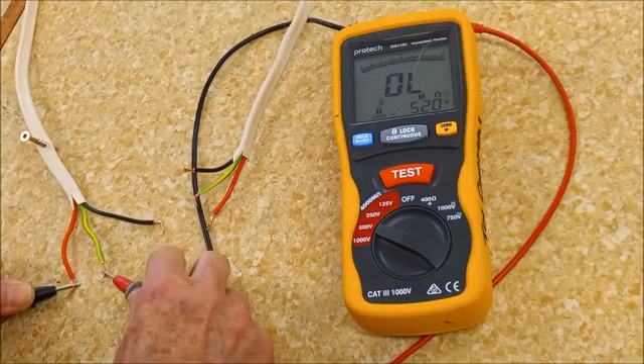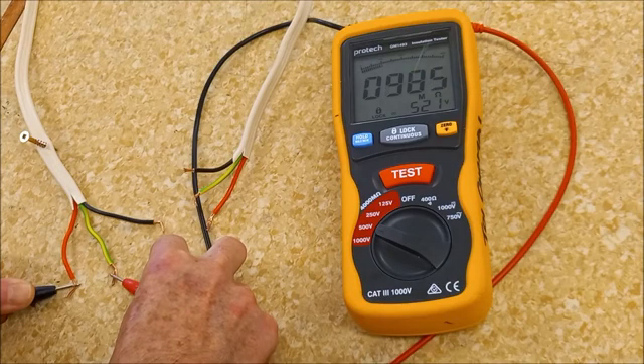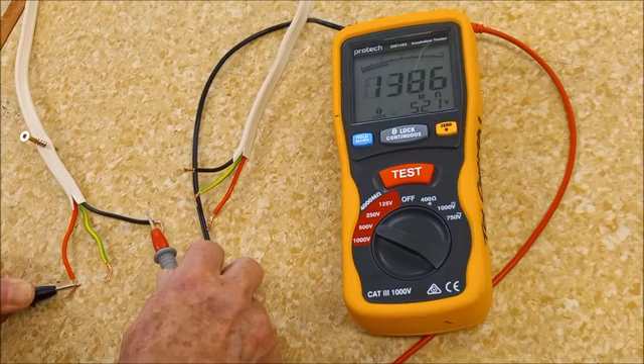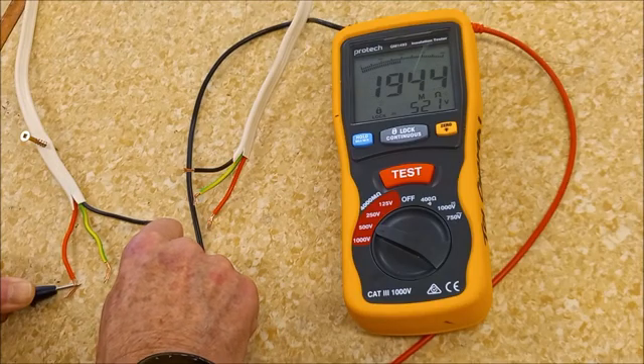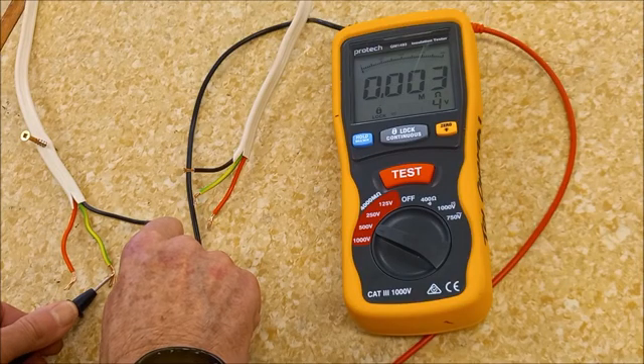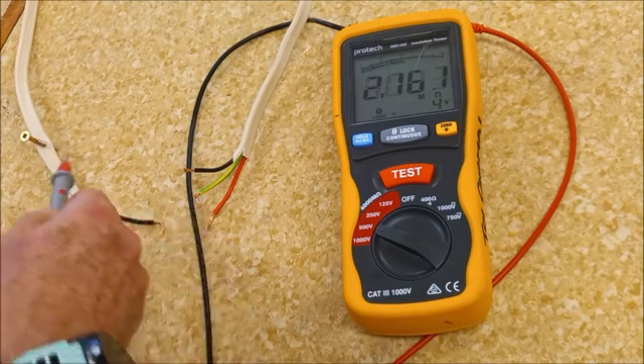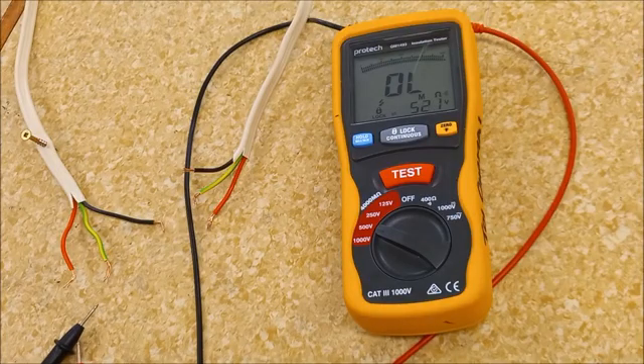Phase to neutral — we have 2,000 million ohms, two gigaohms, much more than we need, much more than one. Oh dear, we found ourselves a fault — that's very, very low resistance, simply because there's a screw through the cable. So it's important that you do all of the tests and have an expectation of what result you're going to get.